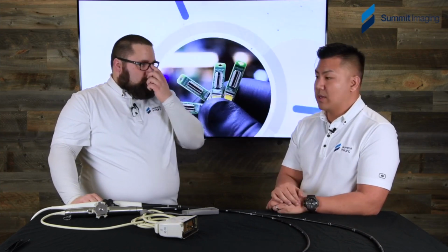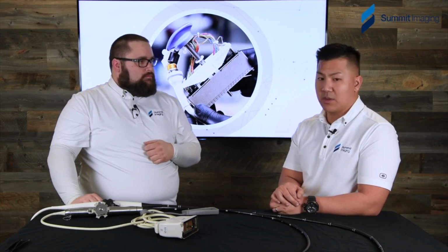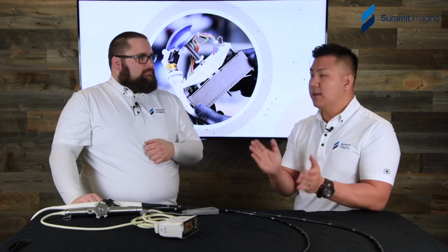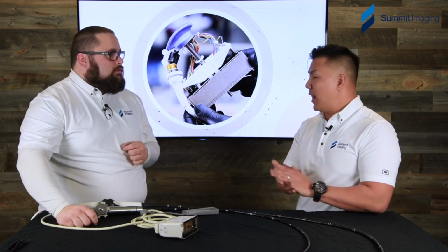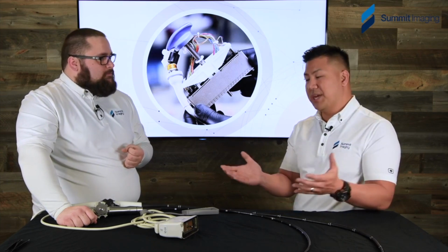There's probably already fluid inside, so the faster you can get it into a service organization to dismantle it and get all the fluid out, the higher the chance that we're going to be able to save the probe. Not only that, it'll be more like a maintenance repair instead of a full extensive rebuild. It becomes a routine, quick disassemble, clean it out, get the electronics back to where they need to be, and then reassemble and it goes back, which is a much simpler process than fully disassembling the entire probe and going through a full repair refurbishment process. Obviously different prices as well.